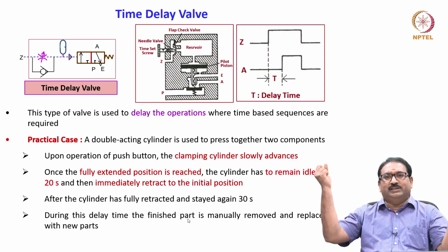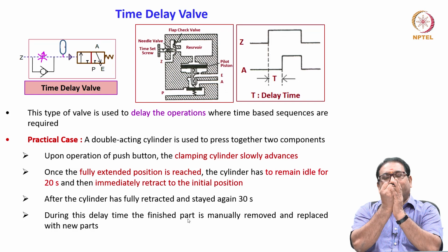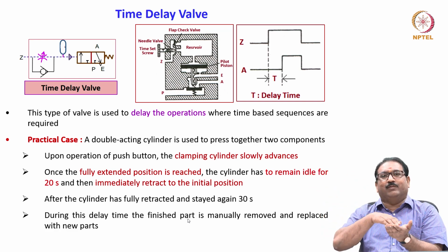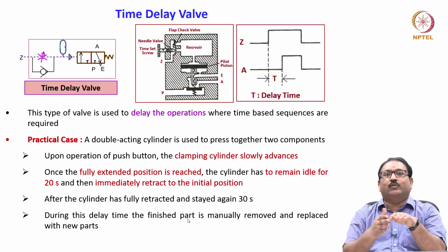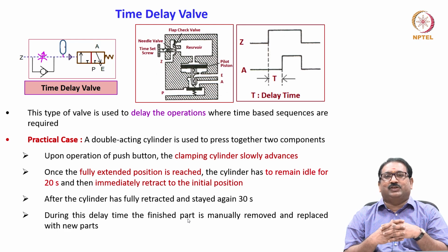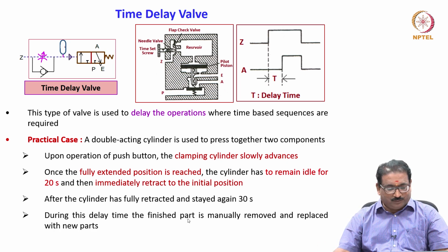Meaning, it will go and extend, press the parts, wait for 20 seconds until both parts stick together, then move back, wait for 30 seconds there, and in that time remove this part and load the new two plates. Here time based sequencing operations are taking place. Such applications call for the time delay valve.